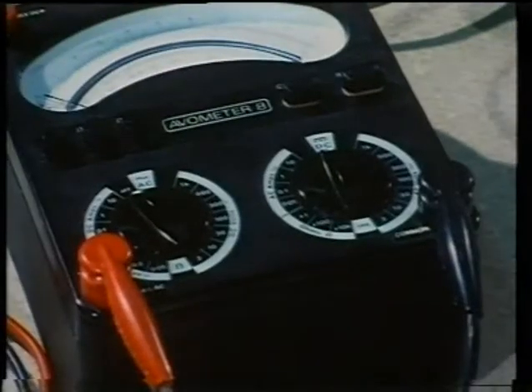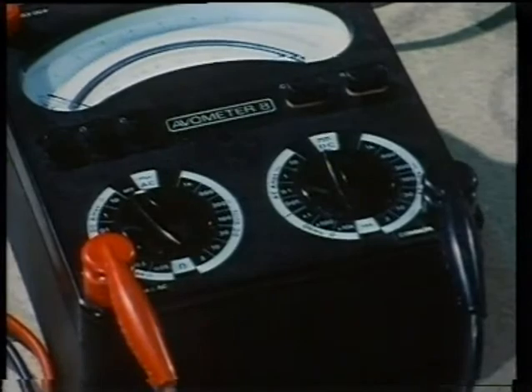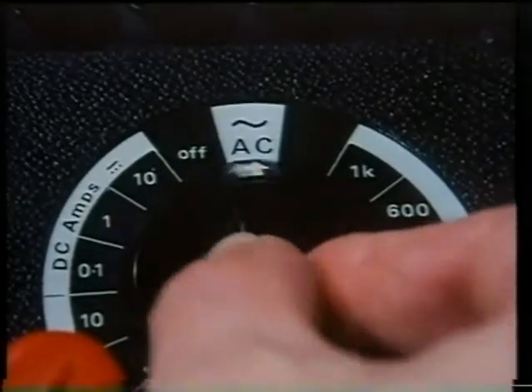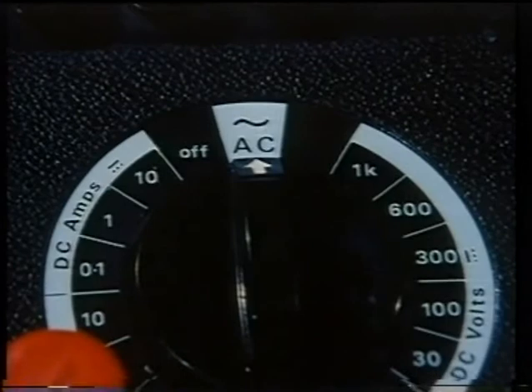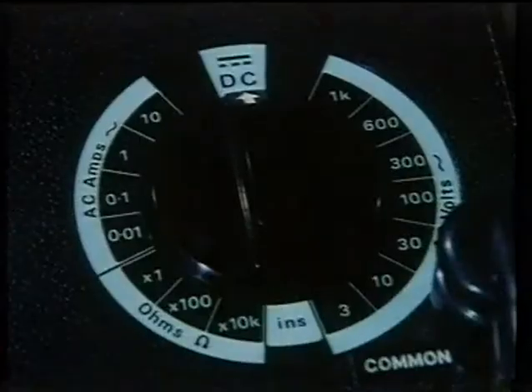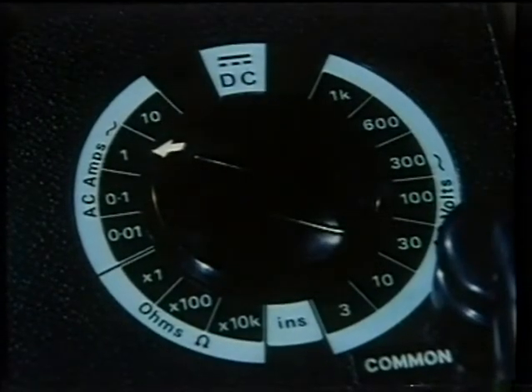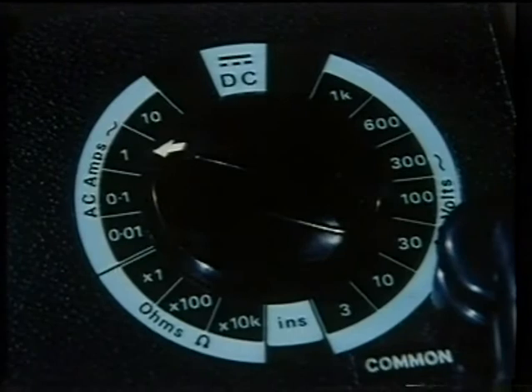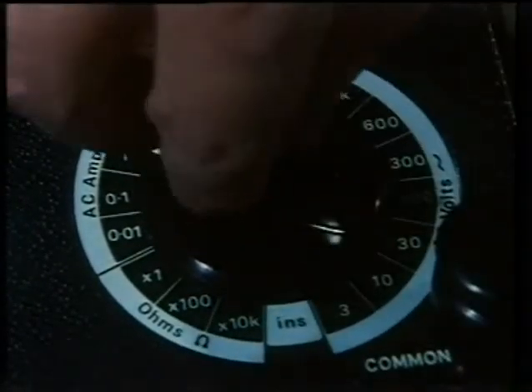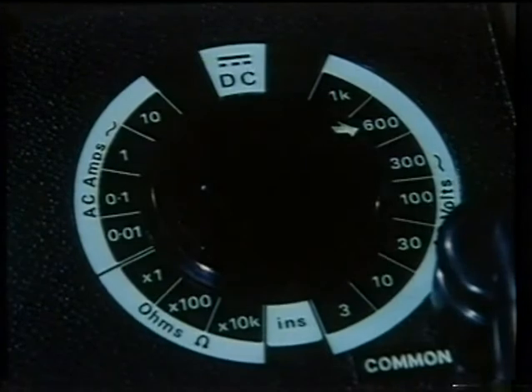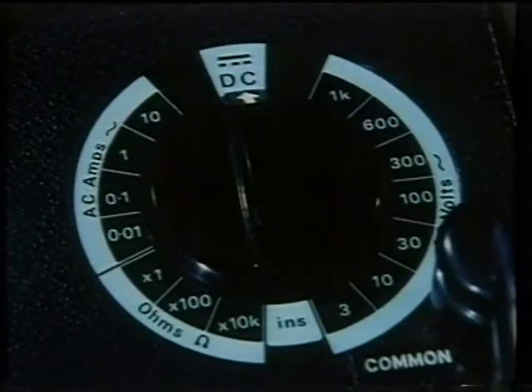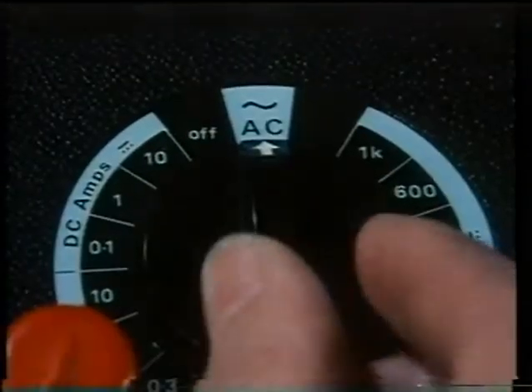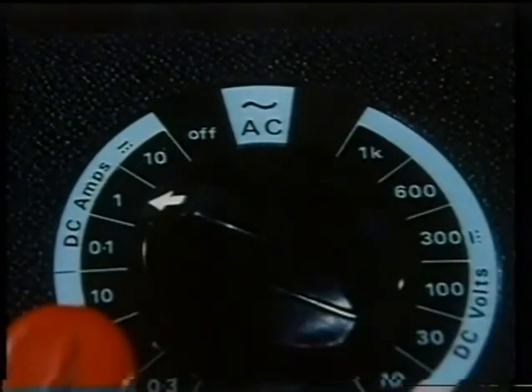Basically, the 2 dials work in combination when setting the meter up for any of its functions. Here, the meter is being set to read AC current by pointing one dial to the AC system and the other dial to the values range, in this case up to 1 amp. Voltage is set by the same dial. Here it is set to 600 volts full scale. For testing a DC supply, the dials change function. First, set the DC system, and with the other dial, select the range, as before.